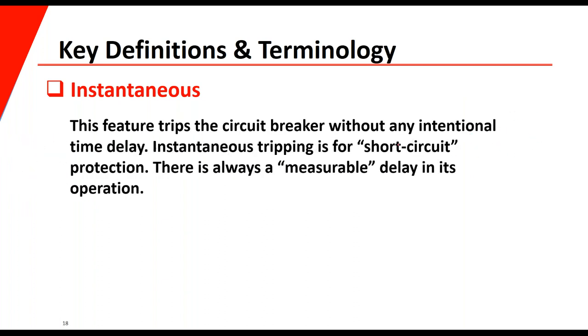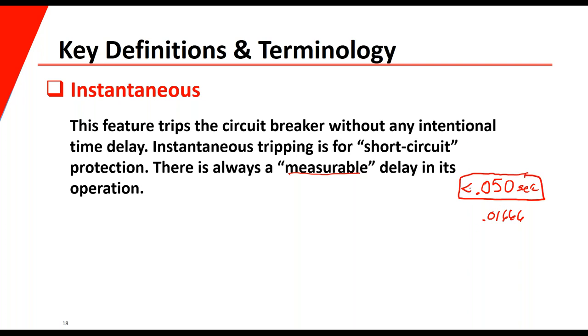Instantaneous tripping is a feature that trips the breaker without any intentional time delay — it trips during a short circuit. There is always some measurable amount of delay in its operation. For most circuit breakers, the number I look for when testing is less than 50 milliseconds — that's about three cycles of current flow. One cycle being 16.6 milliseconds, so three cycles is about 50 milliseconds. If a breaker is not tripping in less than 50 milliseconds when testing the instantaneous device, the breaker may be a little bit slow.